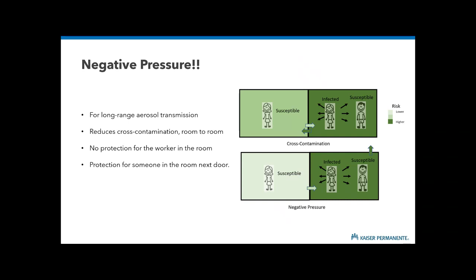Negative pressure does not protect the staff in the room with the patient. If you're already in the contaminated room, congratulations, you're in the contaminated room. You better be wearing a mask. Negative pressure only protects the people in the room next door. If you learned one thing in this hour, learn to repeat that over and over again. Negative pressure does one thing and one thing only. It prevents cross-contamination of the room next door.